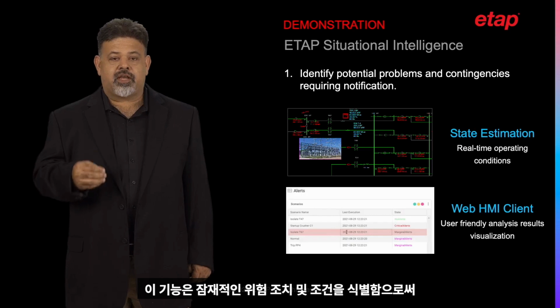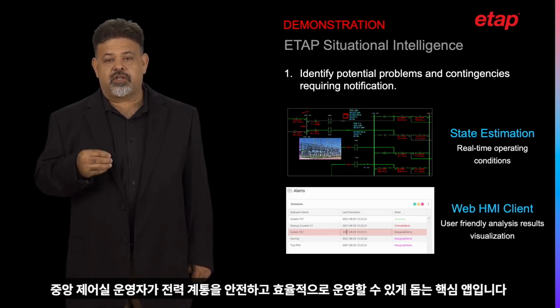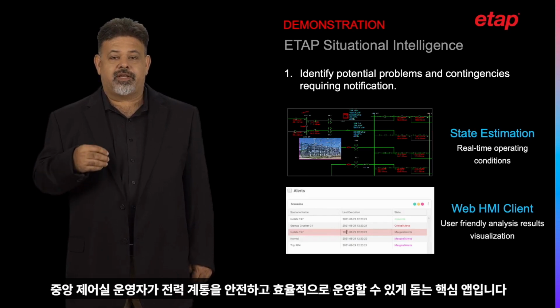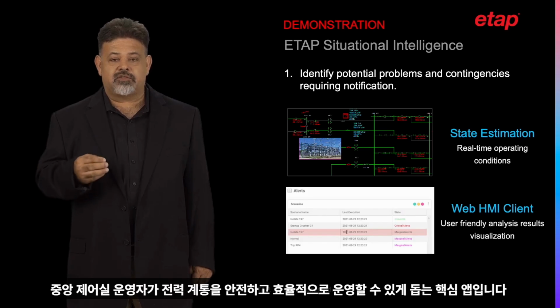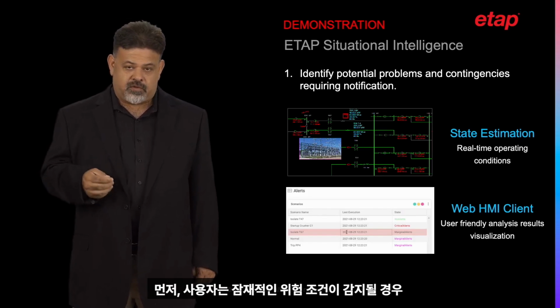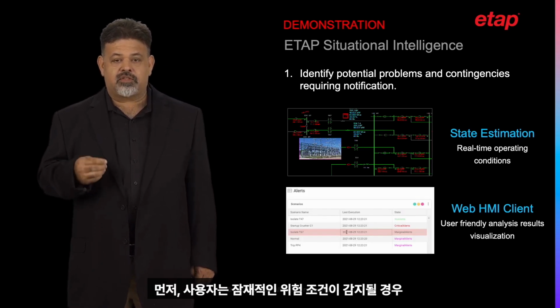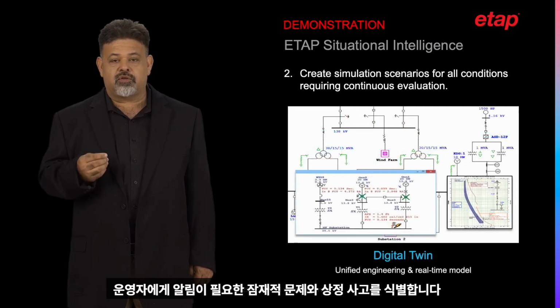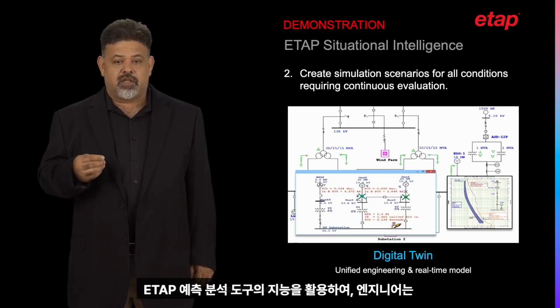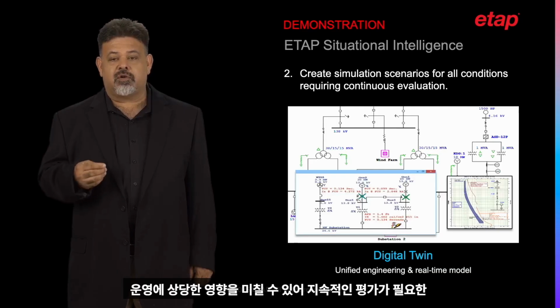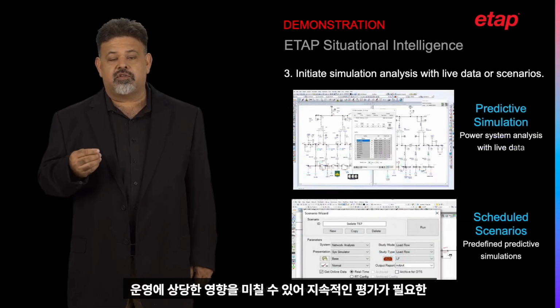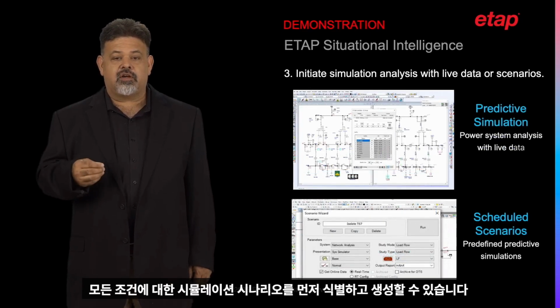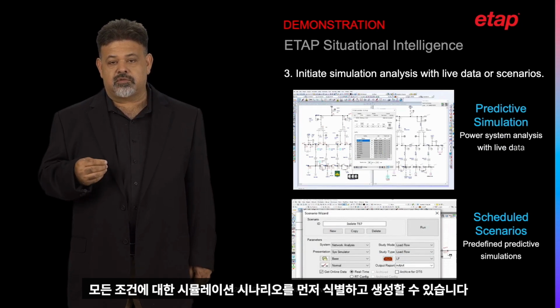This feature is a critical app for control room operators for secure and efficient power system operation by identifying potential unsafe actions and conditions. First, users identify potential problems and contingencies that require the operators to be notified in case a potential unsafe condition is detected. Leveraging the intelligence of the ETAP predictive analysis tools, engineers can first identify and create simulation scenarios for all conditions that will need to be continuously evaluated, as they may cause a significant impact to the operation.